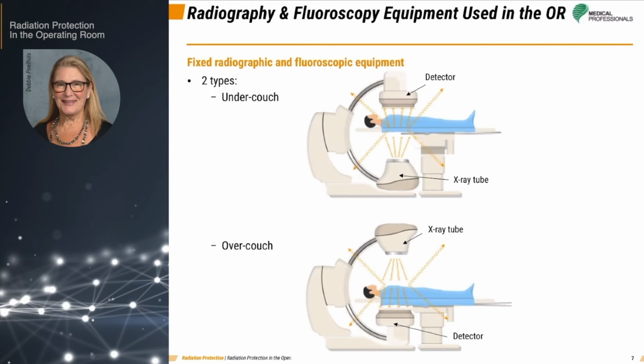There are 2 types of fixed equipment that can be found. The categorization depends on the position of the X-ray tube and the detector in relation to the operating room table. They are called over-couch and under-couch systems. The over-couch configuration consists of an X-ray tube installed over the operating room table. In this case, the detector is under the table and facing the tube. The under-couch configuration consists of an X-ray tube installed under the OR table, and in this case, the detector is over the table, again facing the tube.